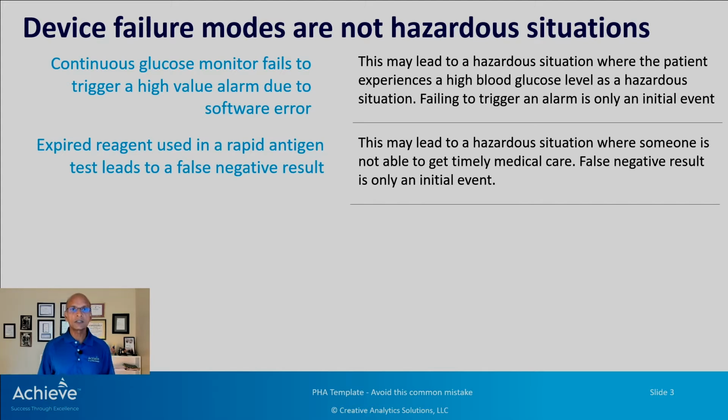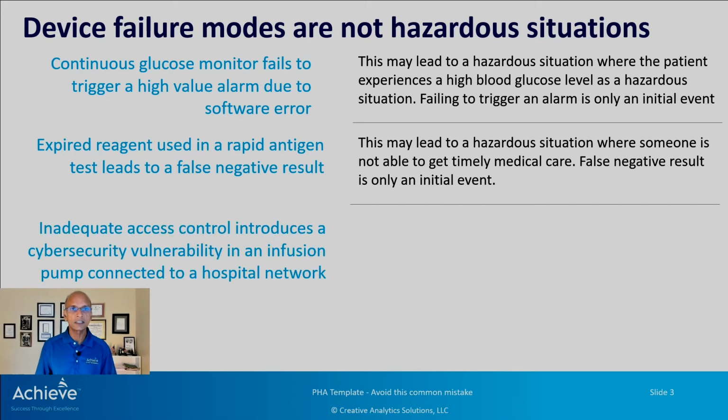Expired reagent used in a rapid antigen test leads to a false negative result. Yeah, so this may lead to a hazardous situation where someone is not able to get timely medical care, but the false negative result is not the hazardous situation. Something more has to happen that leads to a sequence of events and the patient or the user finding themselves in a hazardous situation. A false negative result is only an initial event. Now let's look at this one.